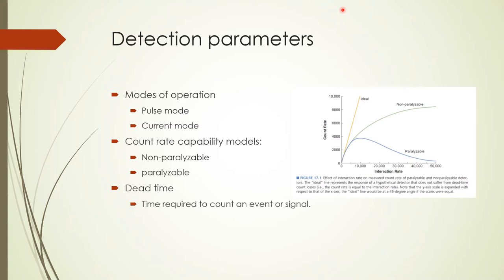During the dead time, other pulses are not counted. The figure shows the plot of an ideal detector where the measured count rate is proportional to the true count rate for a detector operated in pulse mode, and where dead time has no effect. Real radiation detectors can be characterized in terms of count rate capability as either non-paralyzable or paralyzable. The curve describing these two types of radiation detector models is shown on the graph. Non-paralyzable systems ignore signals or pulses during the dead time but will count signals outside the dead time. In high radioactivity environments, the measured count rate continues to increase but at a slower pace than the true count rate.